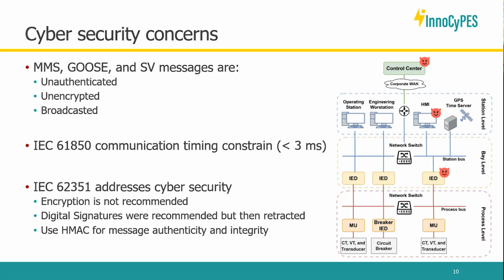This means that when a packet, be it an SV or a GOOSE packet, is sent into the network, we append at the end of the packet a short message. It is used to authenticate the sender and to provide the integrity of the packet.